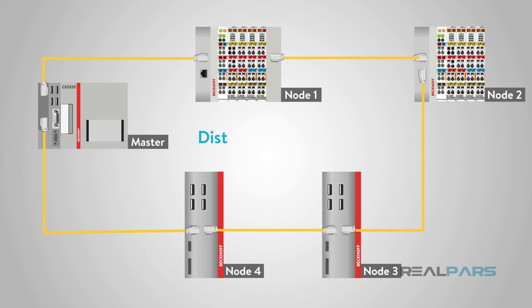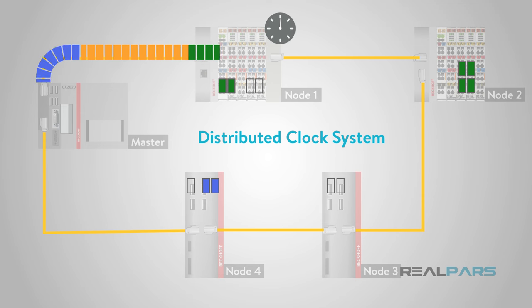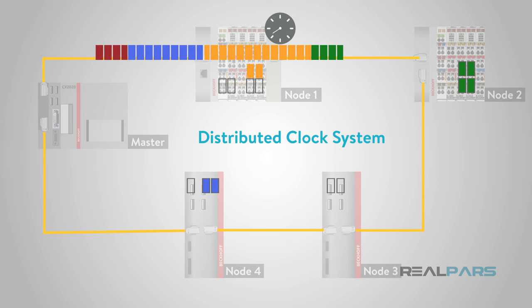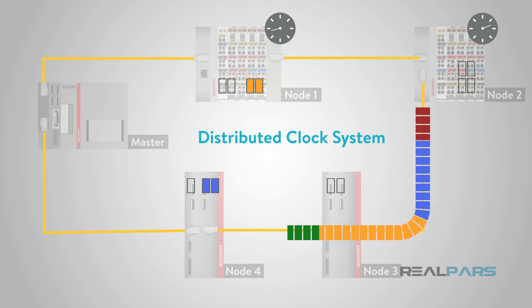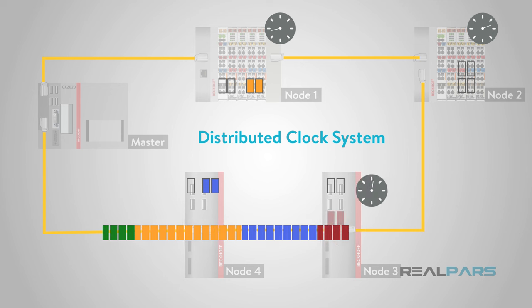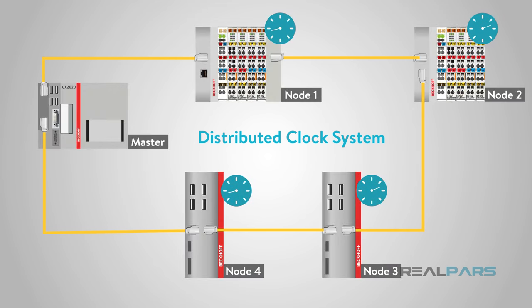EtherCAT also utilizes a distributed clock system. This method allows for low jitter without additional hardware, and it meets the synchronization requirements desired in industrial automation. As the EtherCAT frame passes through each node, the node adds a received message timestamp to its data. Each node adds the timestamp as the message is received, and then each node again attaches a timestamp as the frame moves back through the nodes on the way back to the master. The master then has an accurate delay for each node, as timestamp data is calculated with every data frame transmission.